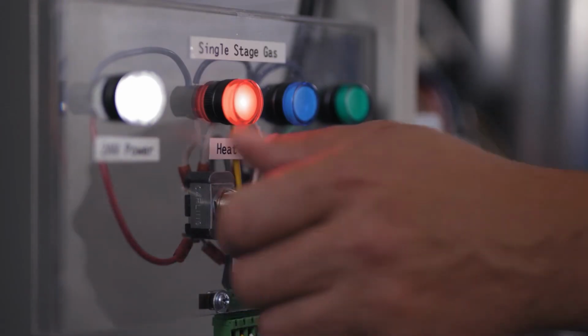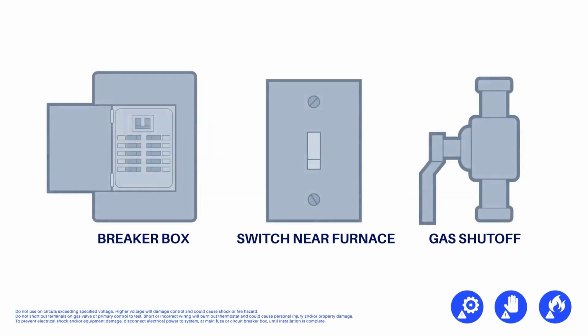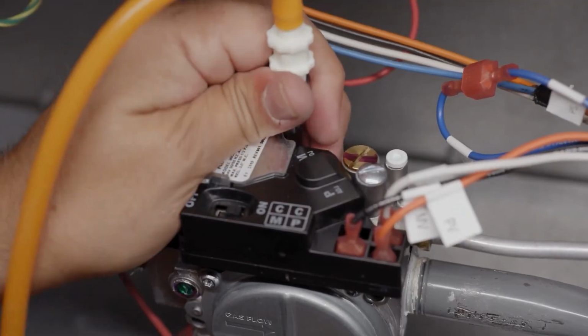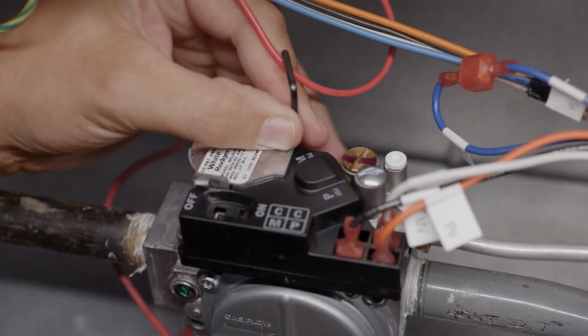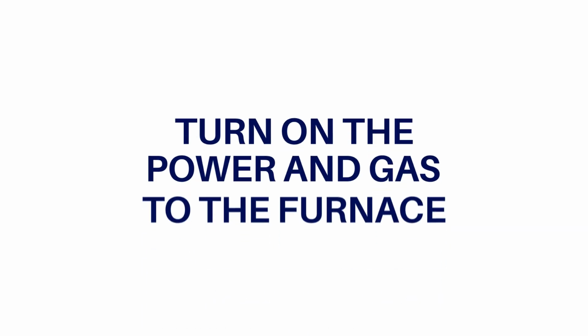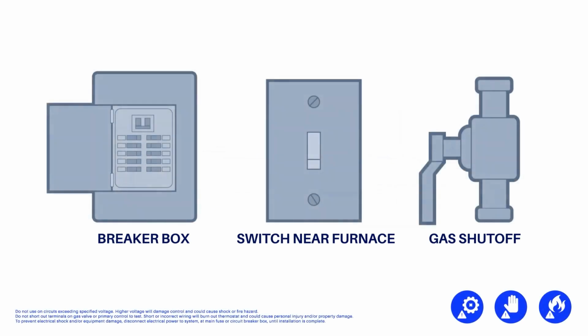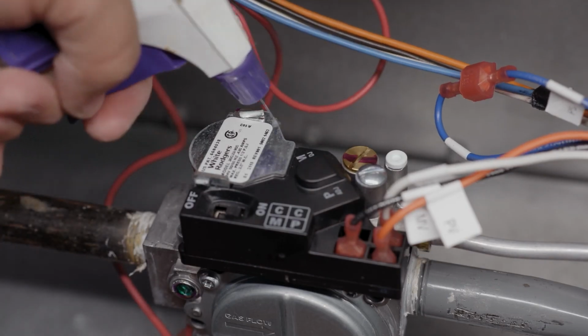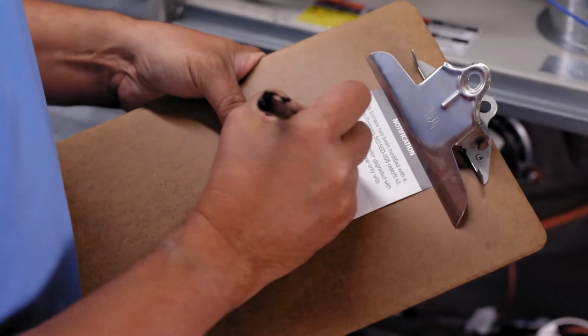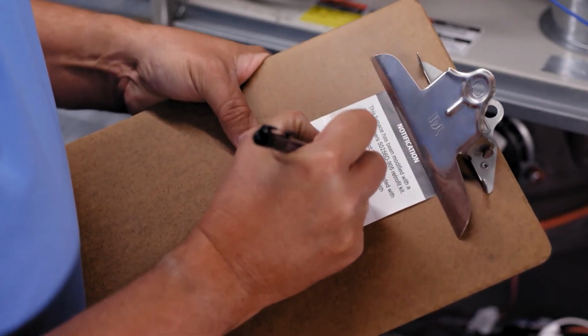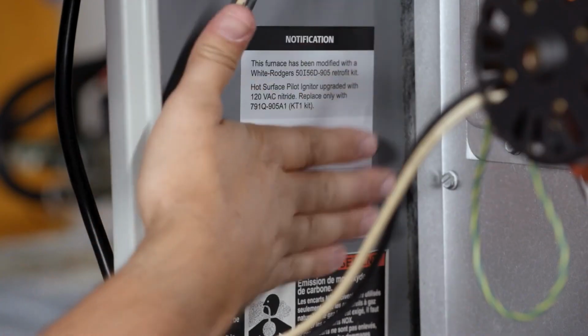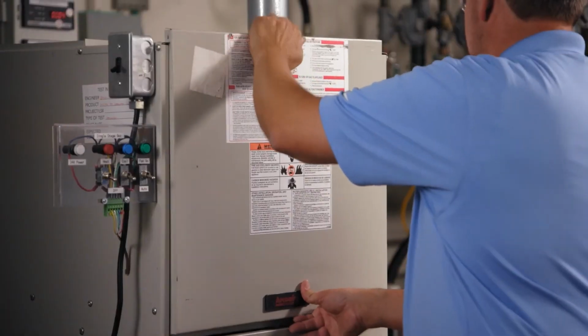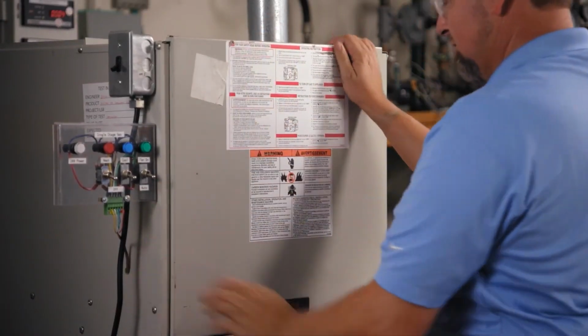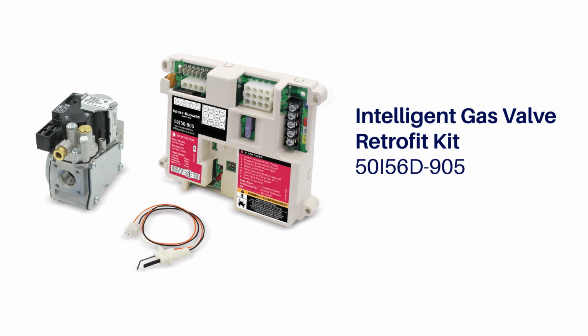Finalize any additional tests desired and terminate the call for heat. Turn power and gas back off. Disconnect the gas manometer following the gas valve installation instructions. Restore the electric power and gas to the unit. Check for gas leaks as necessary. Fill out the installer information on the unit retrofit label and place it in the burner area of the furnace. Reinstall the access panels.